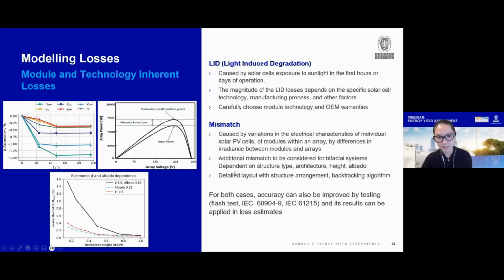With bifacial modules, additional mismatch must be considered—it's very dependent on the structure type, tracker type, architecture, height, and albedo of the site, and how these factors influence the irradiance reaching the back side of the module.